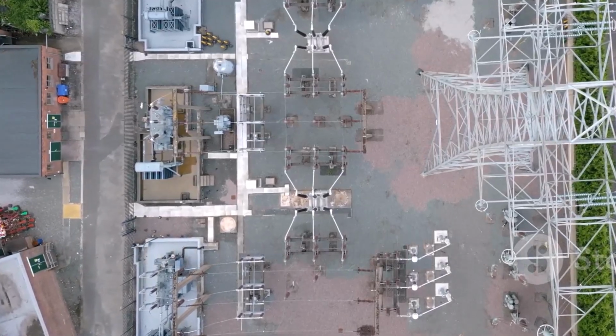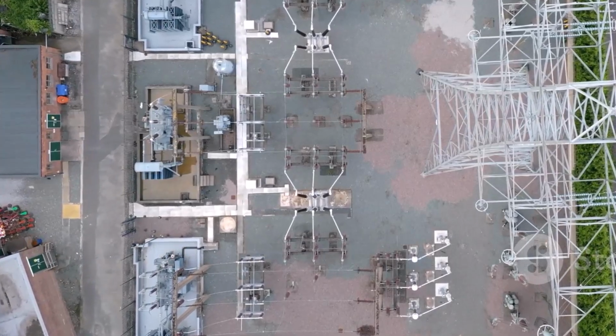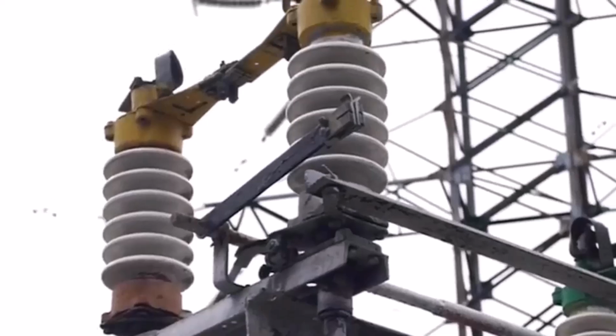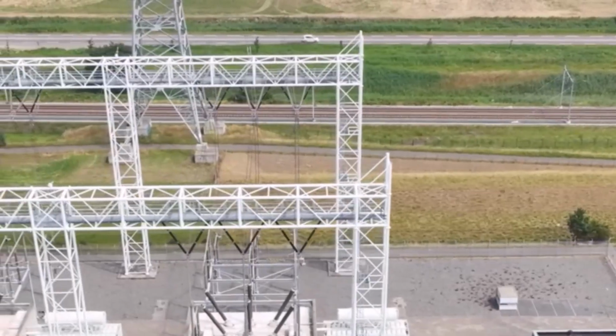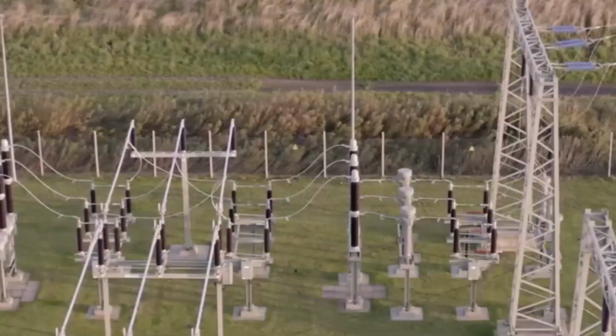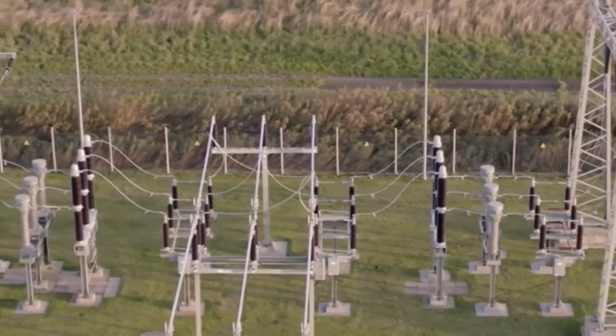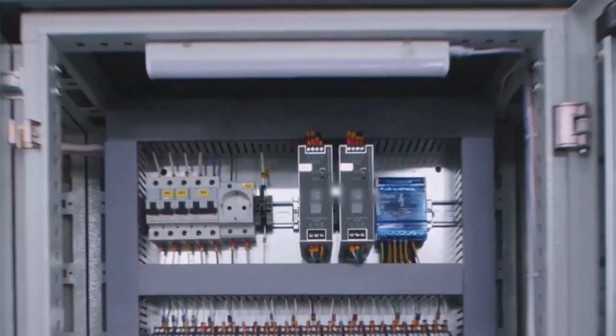Shutting down is as crucial as powering up. First, turn off the load, watch the ammeter drop to 0, trip the main circuit breaker to de-energize the transformer. Voltmeters should read 0. Open the isolator switches starting with the primary, then the secondary, creating a visible air gap.